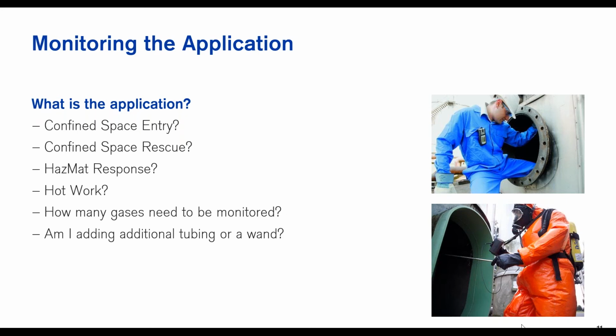They have what they call a thermal conductivity sensor. It's almost exclusive to the gas companies, since they're more or less one-trick ponies—dealing with methane or only a handful of other gases. They know what they're dealing with. So if you're using one of those thermal conductivity sensors, and I'm using a combustible gas indicator, you tell me you've got 65, and I think we're good because we're only at 65% of the LEL.